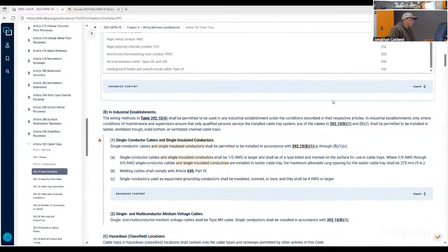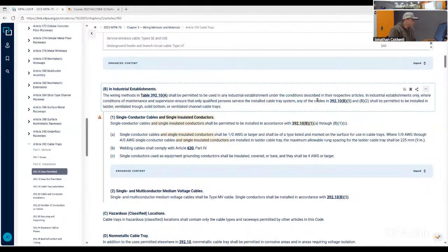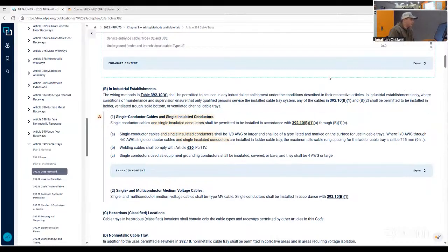In industrial establishments, the wiring methods in Table 392.10(A) shall be permitted to be used in any industrial establishment under the conditions described in the respective articles, in industrial establishments only, where conditions of maintenance and supervision ensure that only qualified persons service the installed cable tray system. Any of the cables in 392.10(B)(1) and (B)(2) shall be permitted to be installed in ladder, ventilated trough, solid bottom, or ventilated channel cable trays.